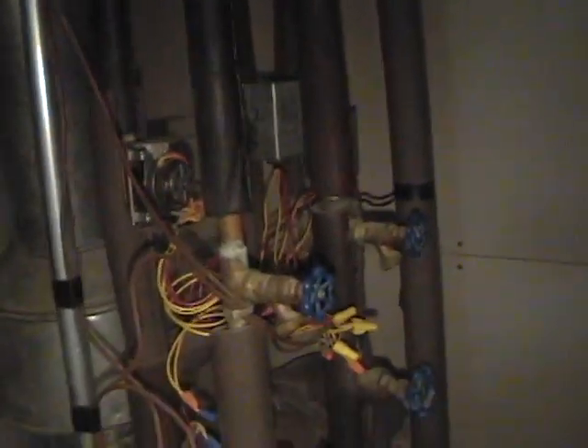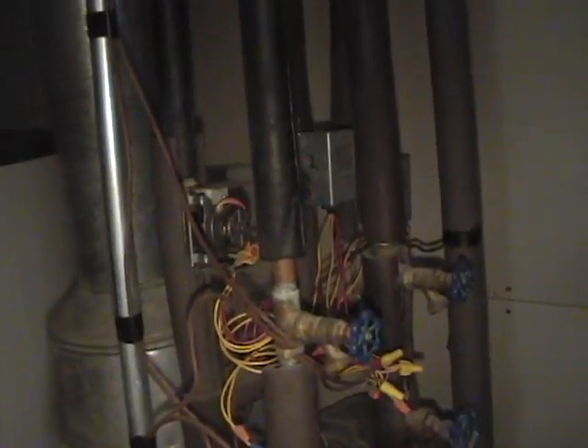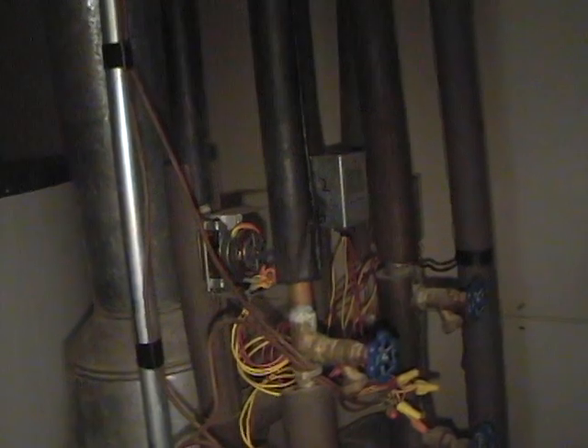And like I said, this also goes to the second floor. Well, to be precise, the attic, because that's where the air handler is for the second floor. And you've got to make sure those pipes, they go a long way, are well insulated, so you don't lose any of the hot water temperature before it gets to the heat exchanger. That wouldn't be all that great.